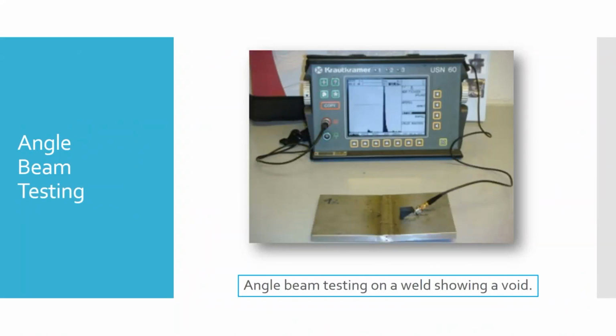So what you can see here on the screen, in this case, is that they are showing a flaw. That's what a flaw would look like. If you're in a non-flaw area, there would be almost nothing on the screen. You'd have a little bit of the little peaks down at the bottom, but you wouldn't have anything else on the screen.